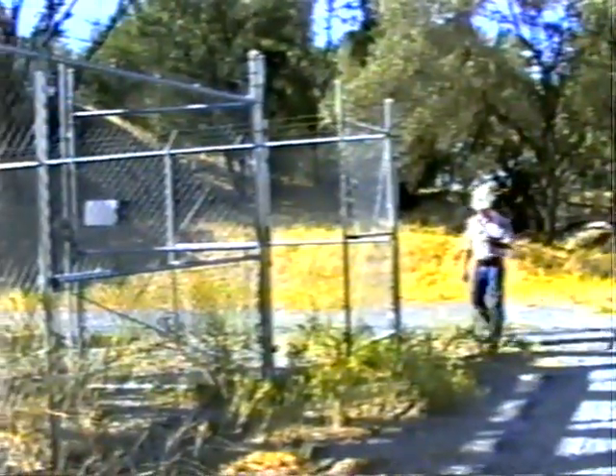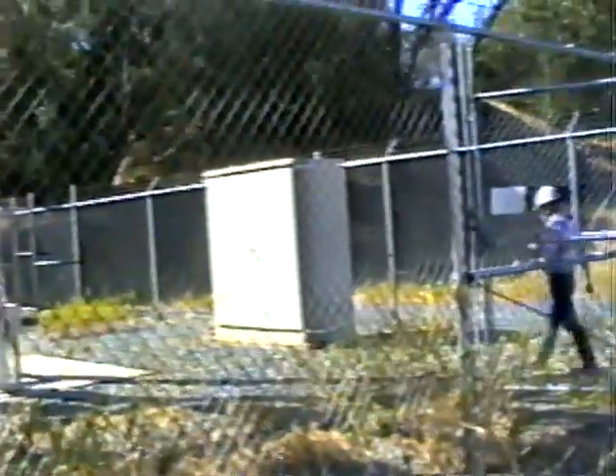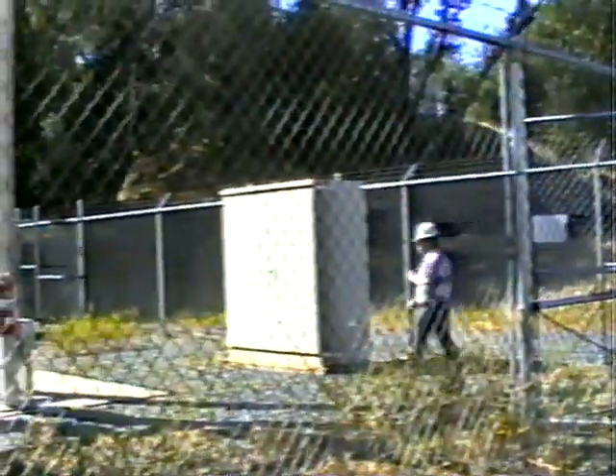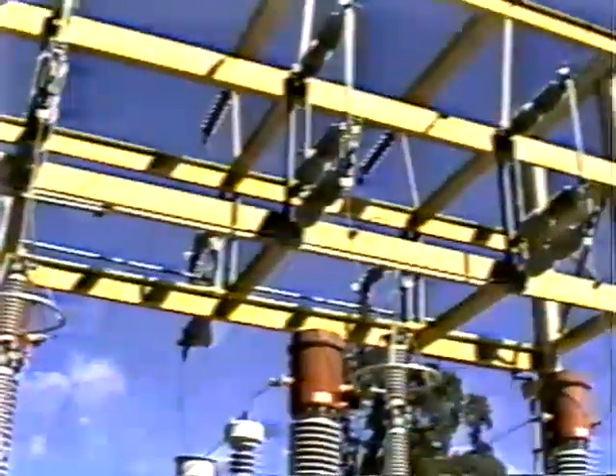Inside these enclosures are the protective relays, and they provide overcurrent protection, ground fault protection. Any time any of these relays sense disturbance in that area, it will open up these main switches that provide power to the mine. On the metering substation here, it's fed down through this power line. The power line is approximately 8/10 of a mile, and it feeds the main substation that's located at the mine.